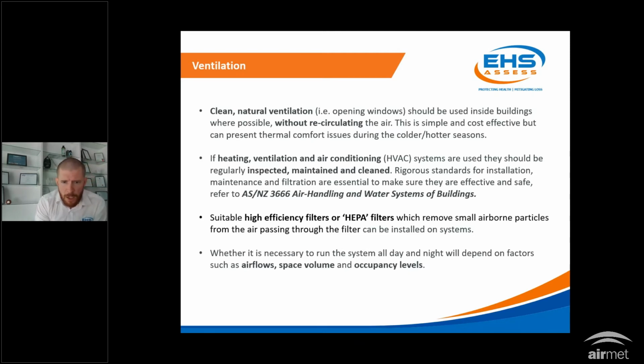There's a lot of talk at the moment about HEPA filters. A HEPA filter is a high efficiency particulate arrester, basically a very high quality filter. They're used extensively in manufacturing and in hospital and healthcare type settings. However, in regular buildings, schools, and offices, HEPA filters on air conditioning systems are not the norm. They come with a lot of challenges, as the filters are very high efficiency, so getting air movement through them isn't something all systems are capable of. So the idea that you just install HEPA filters on all of your air conditioning systems might sound simple and straightforward, but the reality is it presents a lot of challenges. Just bear that in mind.